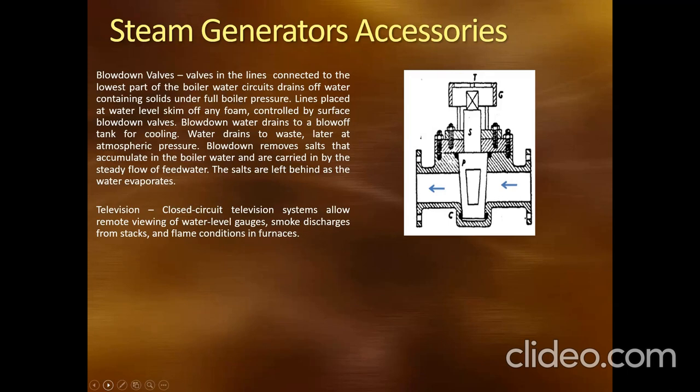Sa boiler ka, di ba? Blowdown, remove salt that accumulate in the boiler water and are carried in by the steady flow of the feed water. Then, the salts are left behind as the water evaporates.